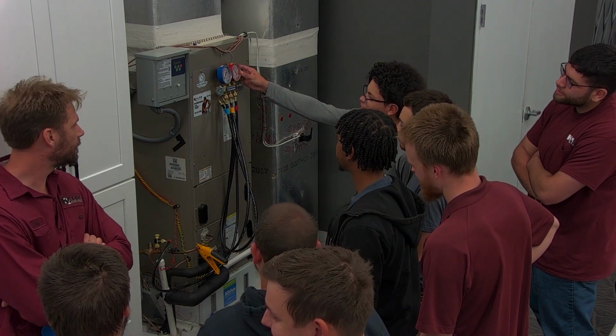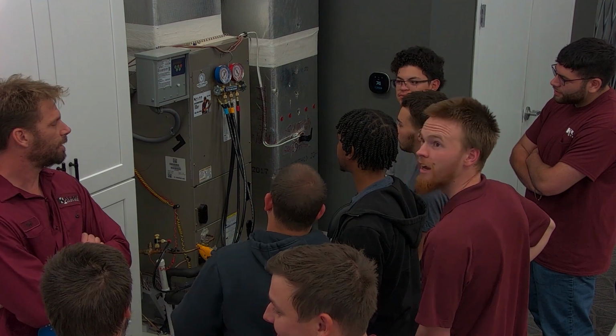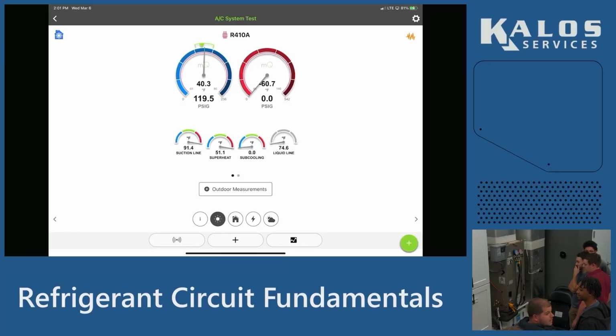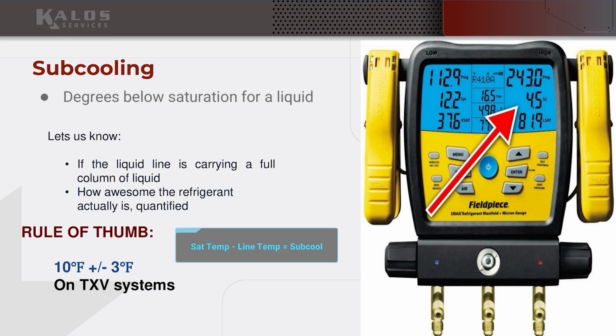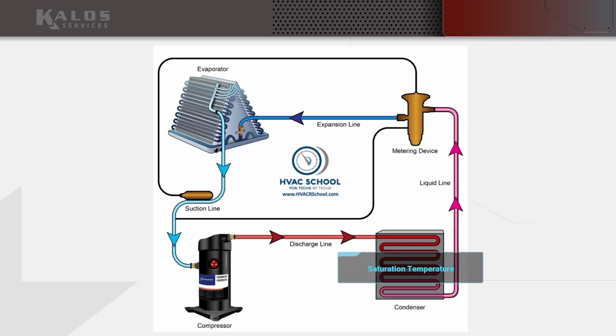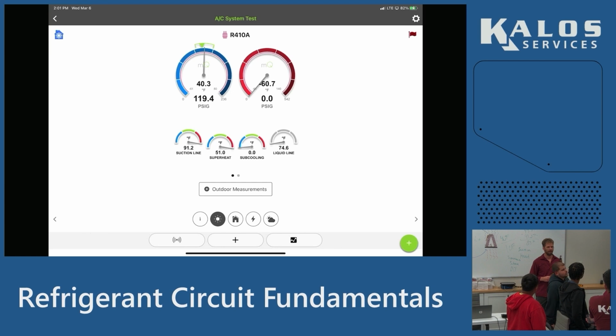All right, we're getting closer, aren't we? Let's calculate subcool. Let's talk some numbers here. Subcool is the difference between the line temperature and saturation. Saturation happens inside the condenser before it's all the way liquid. Line temperature is after it's liquid. So we need our line temperature, one measurement, and our saturation. How far the line temperature comes below that saturation gives us our subcool.